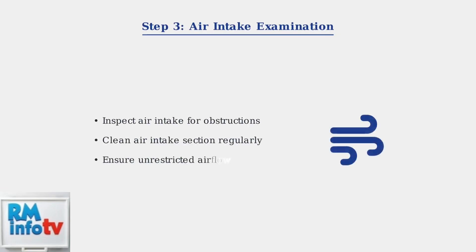Don't forget to check the air intake system. Any obstructions in the air intake can prevent proper combustion and trigger error code 13. Regular cleaning of the air intake section helps maintain efficiency.